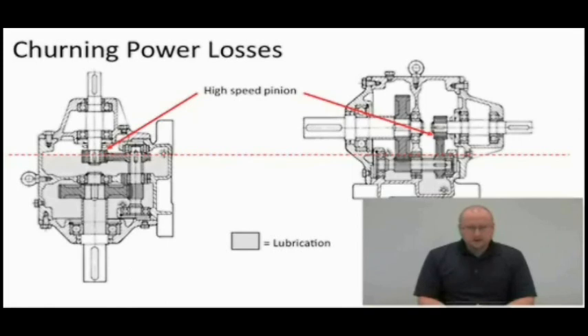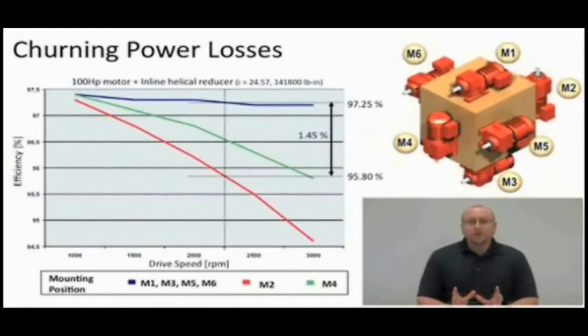With a particular gearbox, you're going to see that there are different efficiencies for different mounting positions. Here are some measured values for a particular gear motor, a motor and gearbox combination, showing the different efficiency levels for different mounting positions. You can see that a horizontal mounting position has the highest efficiency, and vertical mounting positions have a lower efficiency, depending on whether your high-speed pinion is completely submerged in the oil or not. That's not really a trick, but it's another thing that really affects efficiency in a gearbox: how it's mounted. So that can play a great part in your efficiency.